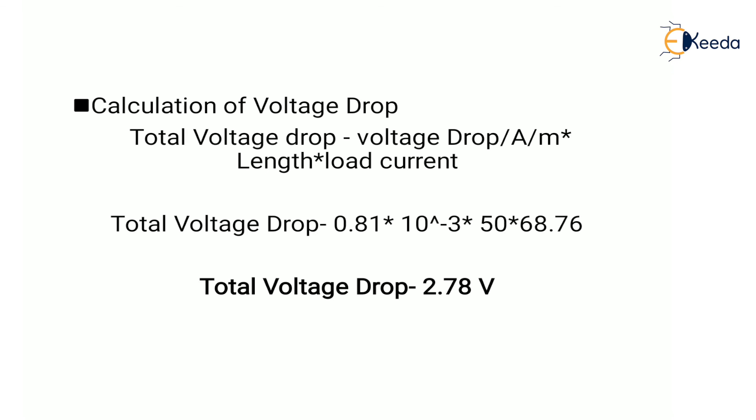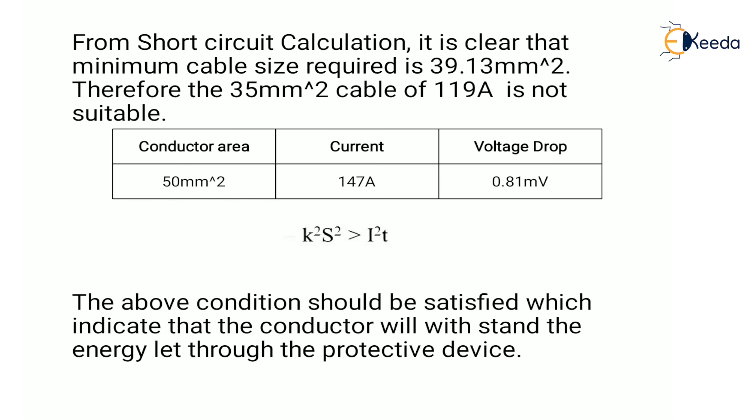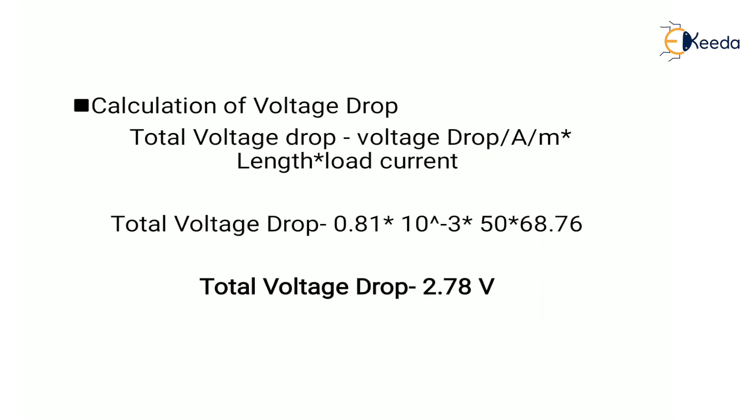Next, we calculate the voltage drop. The formula is: voltage drop = (mV/A/m value) × length × load current. So: 0.81 × 10⁻³ × 50 × 68.76 = 2.78 V. The voltage drop should be within the permissible limit. Thus, the final cable selection is based on current carrying capacity, voltage drop, and short circuit rating.